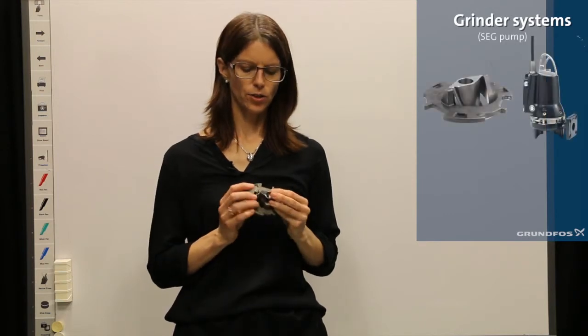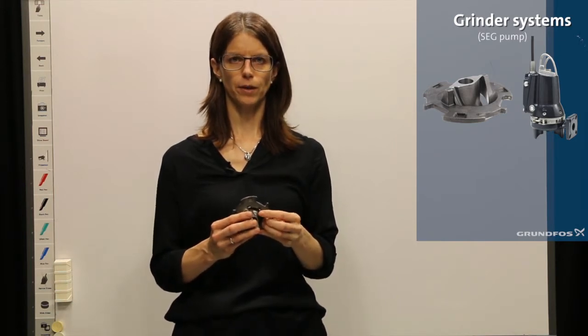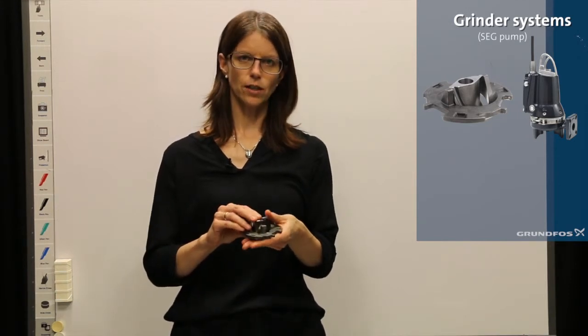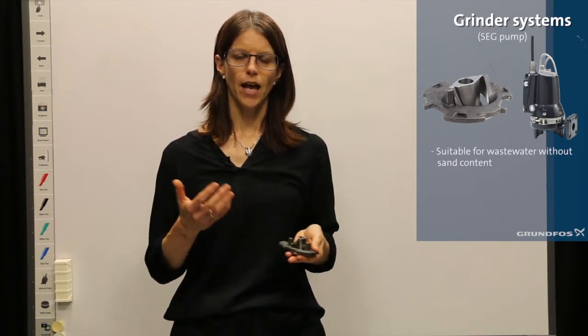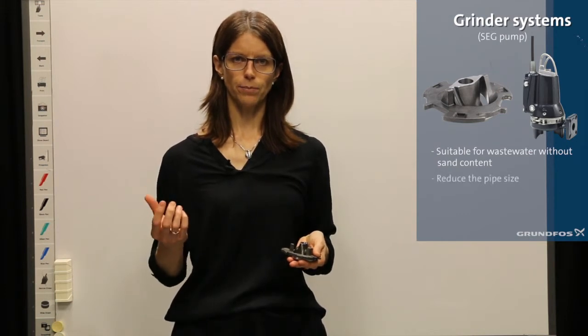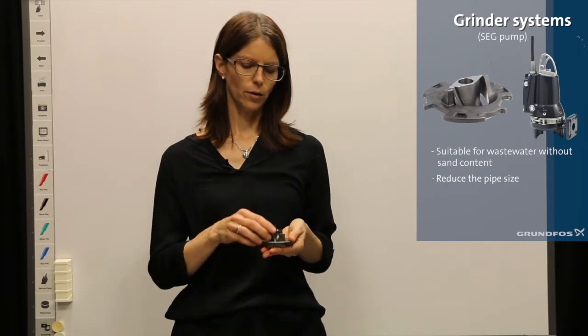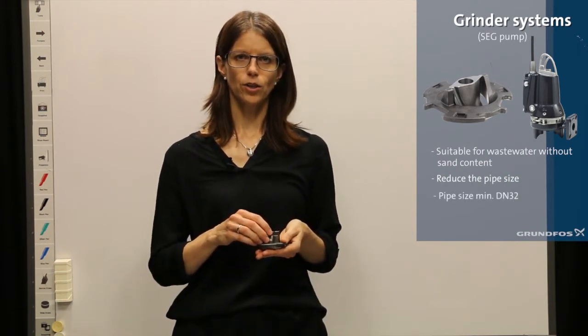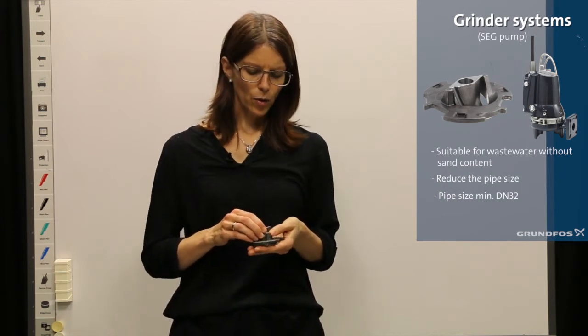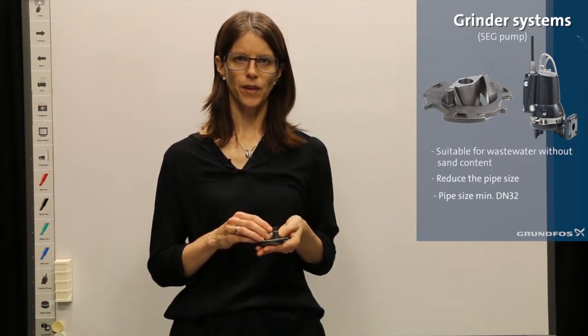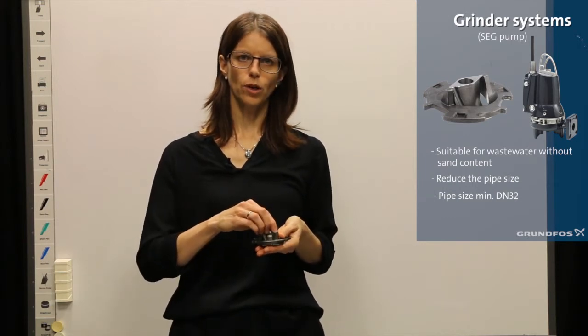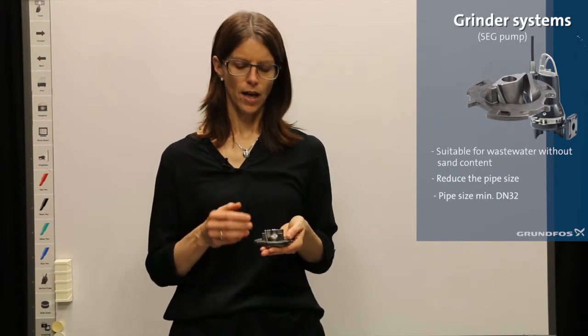The last part of this video is about grinders. Here you see the cutter system used in the SEG grinder pump. Using this cutter system, solids in the wastewater are fragmented into very small pieces, which means the pipe size in the system can be considerably reduced — with the SEG grinder pump you can use DN32 pipe. When operating a grinder pump it is very important that the flow is not too high, otherwise the cutter system will have problems processing the solids and the pump will stop.